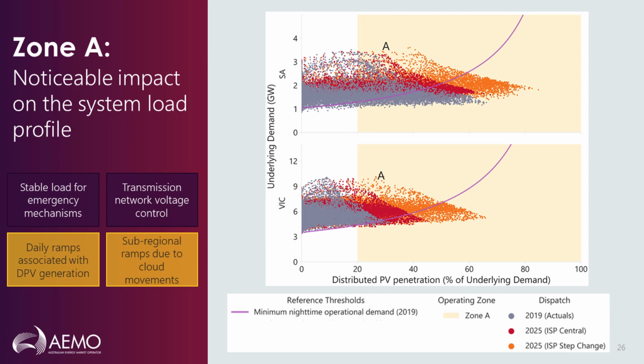The first zone we've identified corresponds to when DPV penetration crosses the 20% mark. From this point, DPV is beginning to noticeably impact the system load profile. As penetrations continue to increase, specific operational challenges may arise. So increasing levels of DPV online during low underlying demand periods begin to impact the availability of stable load blocks, which are necessary for these emergency mechanisms to work properly if rare, high-impact, low-probability events were to occur in the daytime. The 2 key mechanisms we're talking about here are emergency frequency control schemes, as well as system restart.